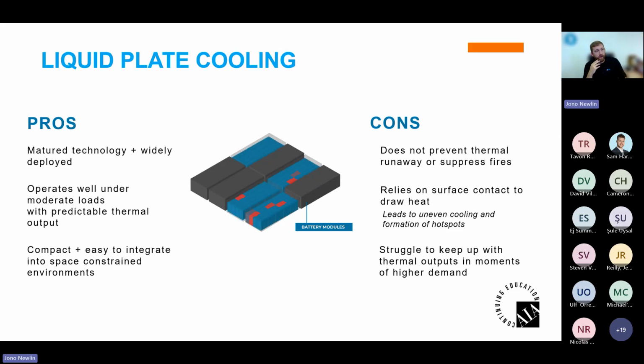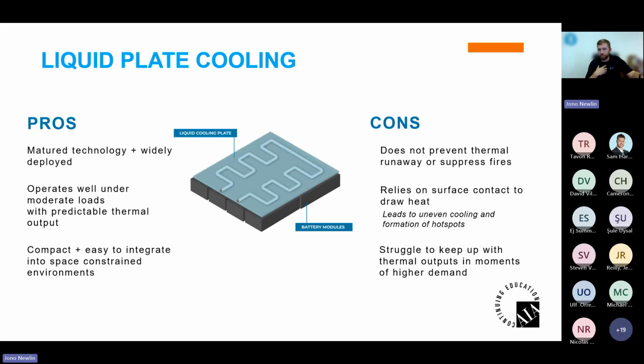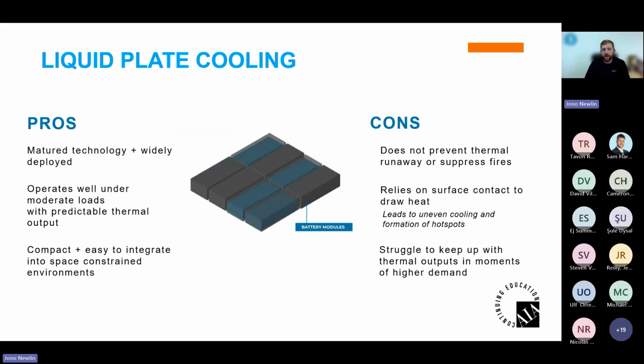And actually, in the earlier slides on the causes, there's been, for example, the Tesla Megapack. I don't pick on Tesla. They just published this report and EPRI picked that up. But there was a liquid plate cooling leak that got liquid glycol onto a bus bar that caused a short, that then caused a thermal runaway, that then caused a large-scale fire. By large scale, I mean into the containerized system.